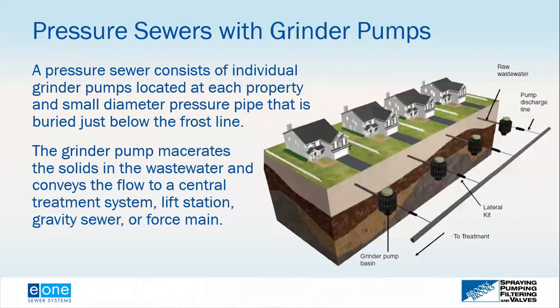The pressure sewer system, on the other hand, uses pumps. There is a grinder pump located at each property and a small diameter pipe buried just below the frost line. The grinder pump macerates solids in the wastewater to very fine particles and conveys it to either a central wastewater treatment system, another collection system, a gravity sewer, a lift station, a force main, or a gravity manhole. Because the solids are macerated and a pump moves them, the pipe for a low pressure sewer system is much smaller in diameter than a typical gravity sewer system.